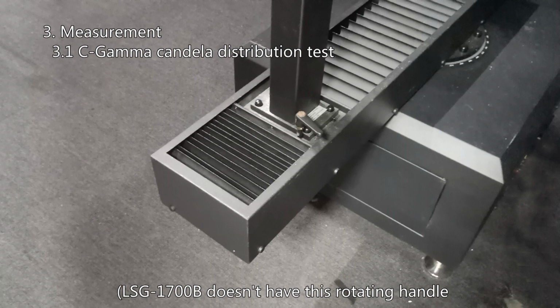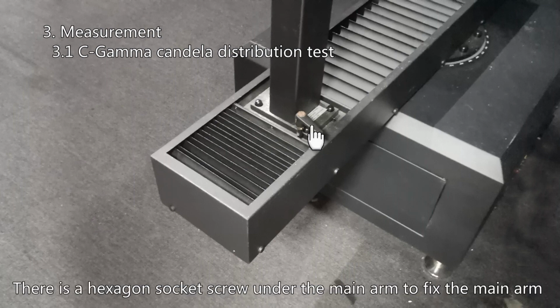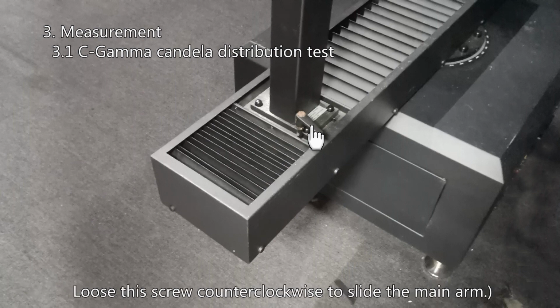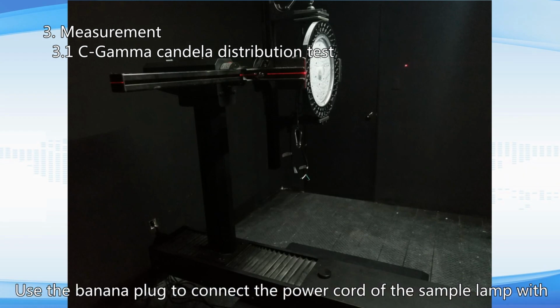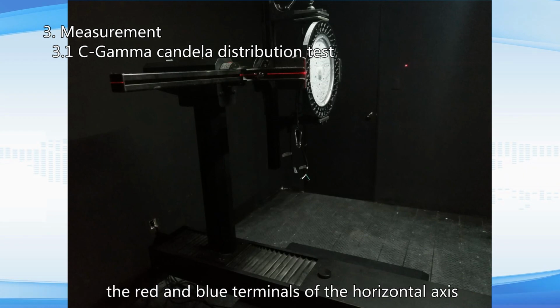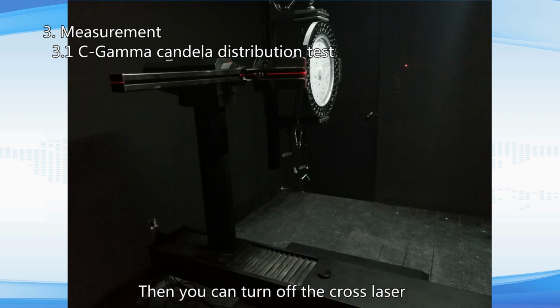LSG1700B doesn't have this rotating handle. There is a hexagon socket screw under the main arm to fix the main arm. Loosen this screw counterclockwise to slide the main arm. Use the banana plug to connect the power cord of the sample lamp with the red and blue terminals of the horizontal axis. Then you can turn off the cross laser.